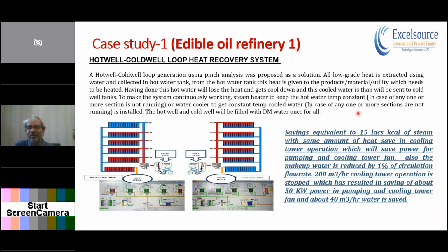And so the desirable output that we have received is the equivalent amount of steam, 15 lakhs kilocalorie, and we have stopped the 200 meter cube per hour of cooling tower operations, which was resulting in power loss as well as water losses. So we have achieved three targets: heat conservation, water conservation, and electricity conservation. Heat conservation, we have saved steam requirement. We have basically reduced the water, which is scarce.